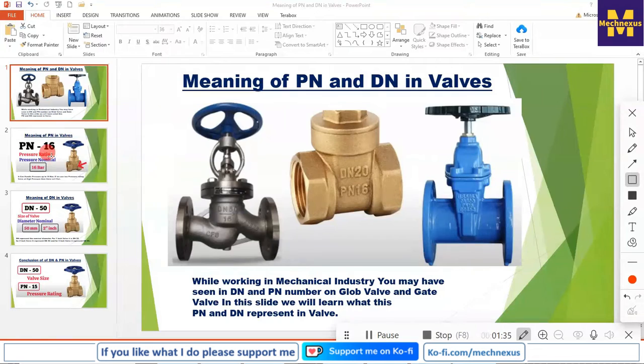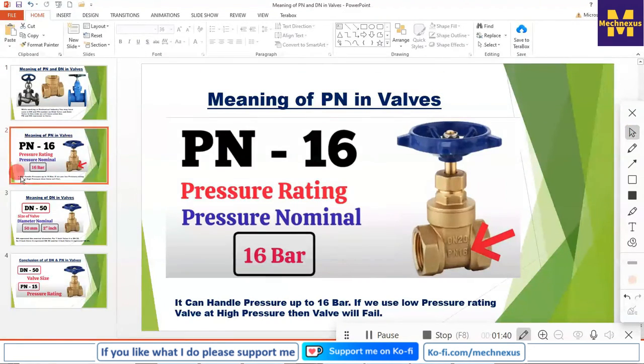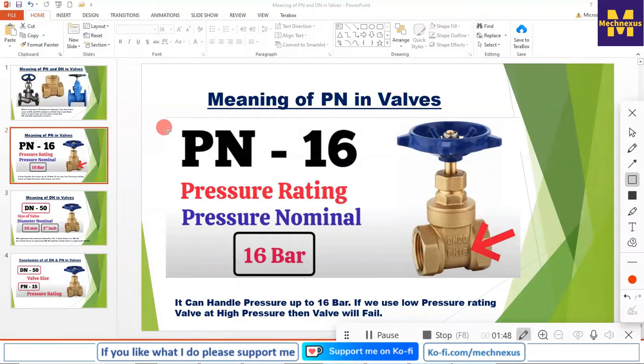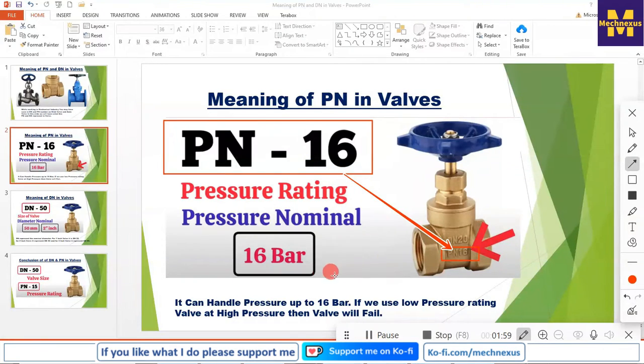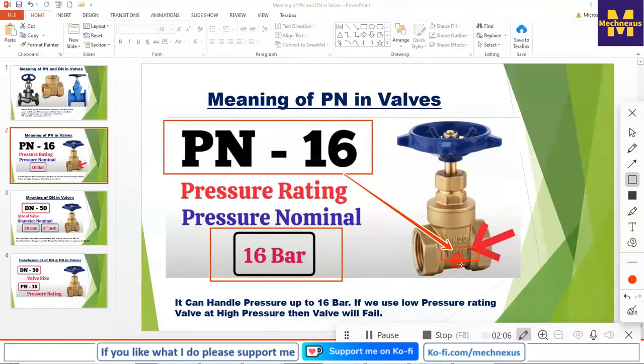Let's move to the next slide and understand what is the meaning of PN. Basically, the PN number represents the pressure rating, which stands for Pressure Nominal. If it is mentioned on a valve as PN 16 — which you can see here — it means that this valve can handle a pressure of 16 bar. That is the simple meaning of PN. If it is PN 20, then it can handle pressure up to 20 bar.